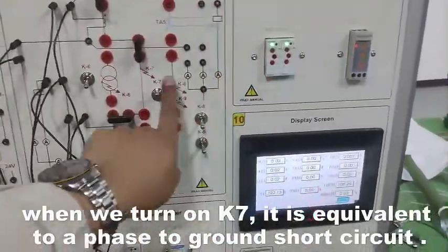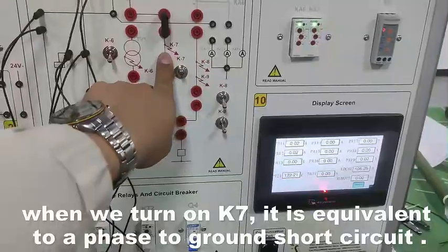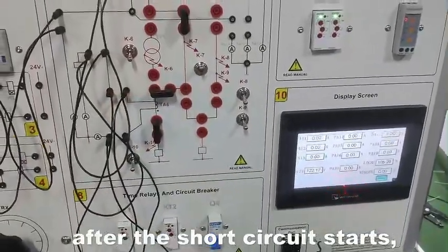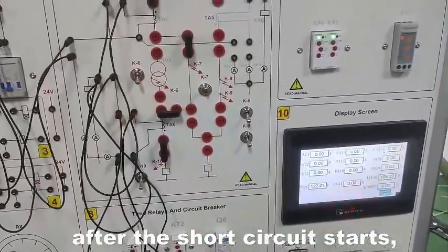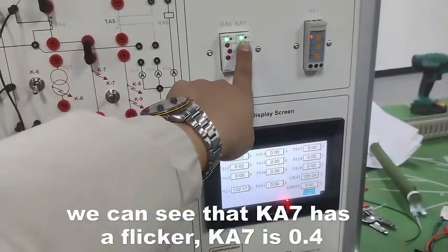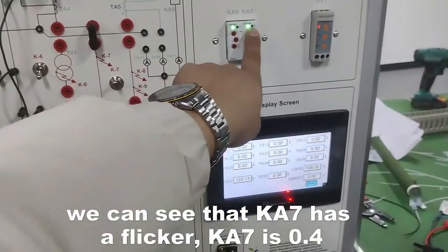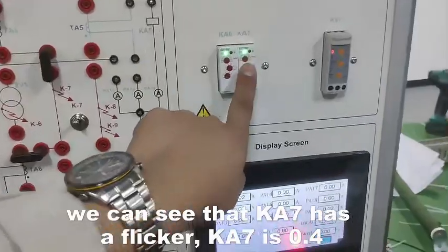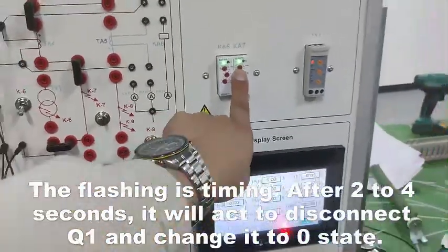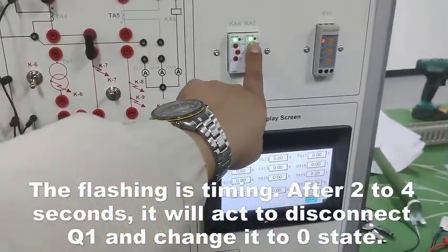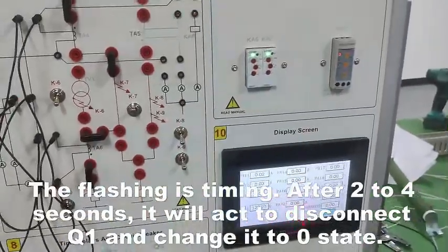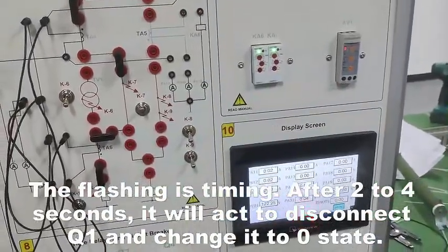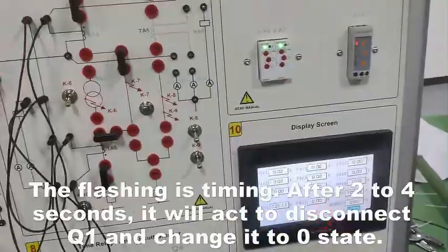When we turn on K7, it is equivalent to phase to ground short circuit. After the short circuit starts, we can see that KA7 has a flicker. KA7 is 0.4. The flashing is timing. After 2 to 4 seconds, it will act to disconnect Q1 and change it to 0 state.